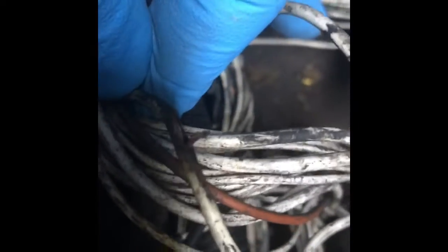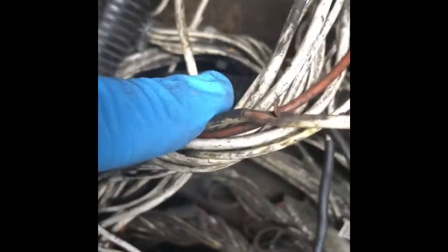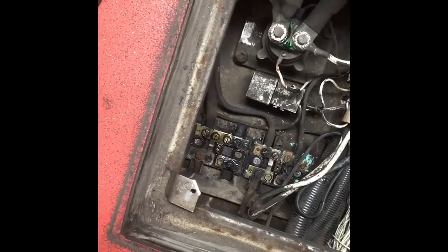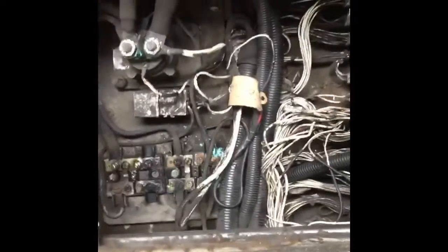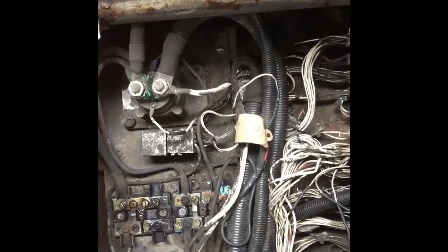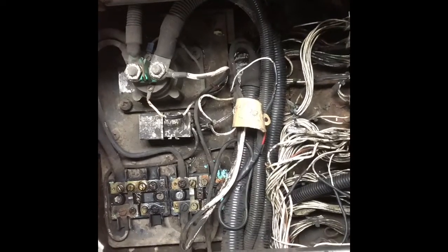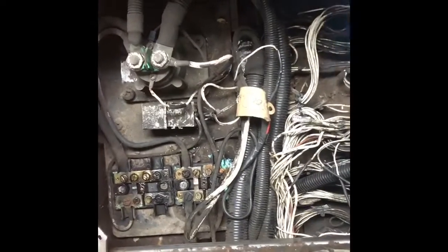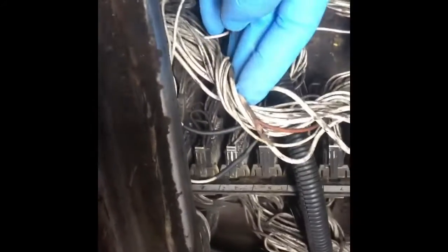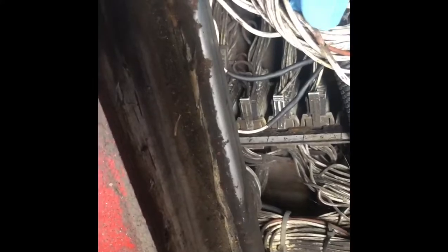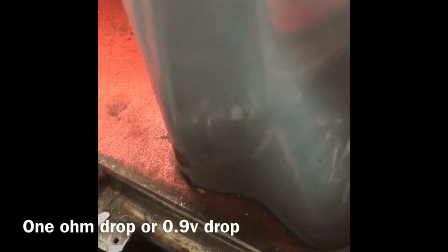And as you can see, it's been shorting against the floor. It's rubbed and it's shorting against the floor. So we've had a problem with a short circuit that's now become what we refer to as an open circuit, because it's shorted so many times that it's effectively broken the cable and broken our connection. So that will need to be repaired. But as you can see, almost a quarter of its wiring is broken, yet when we do our resistance test, we've only got a 1 ohm drop.